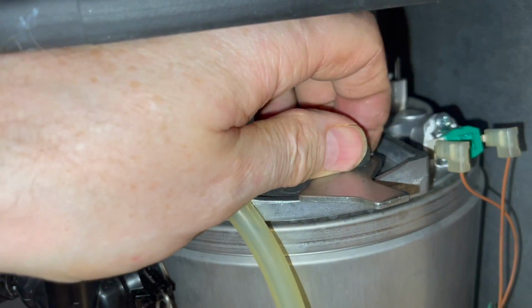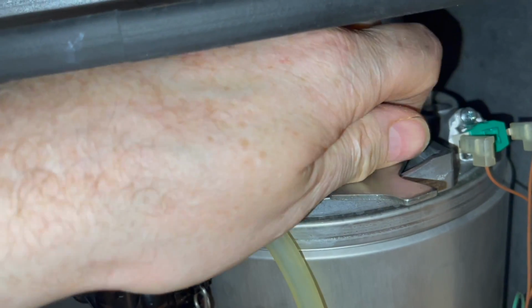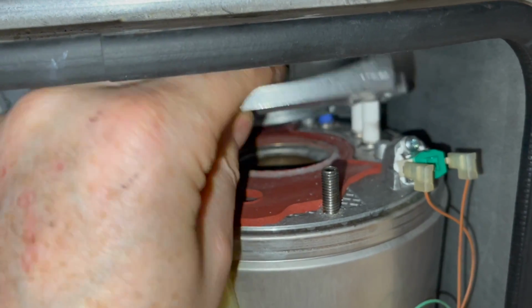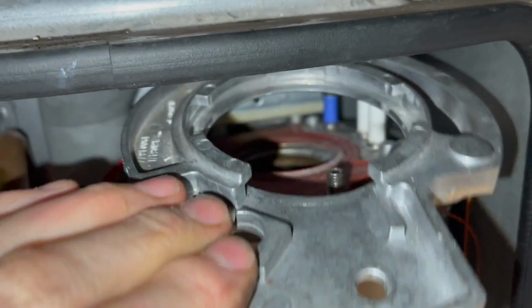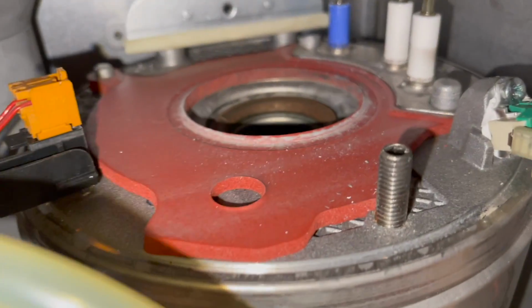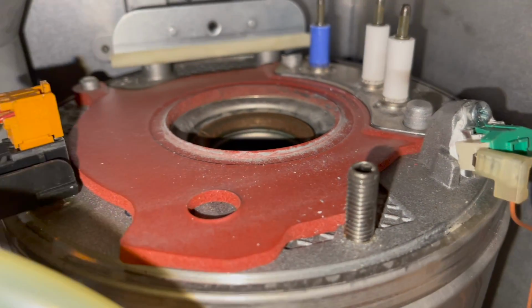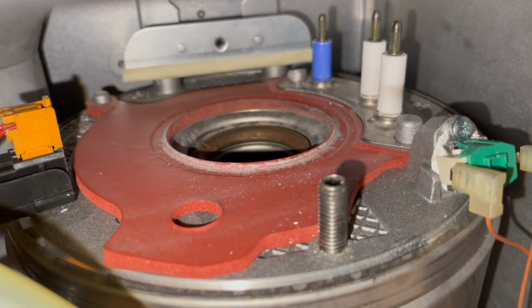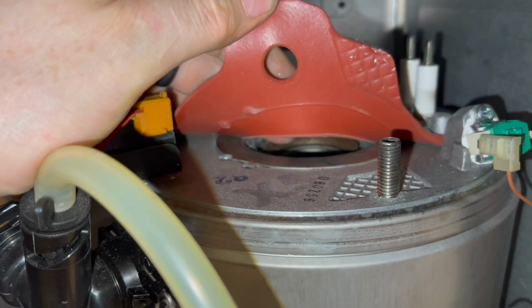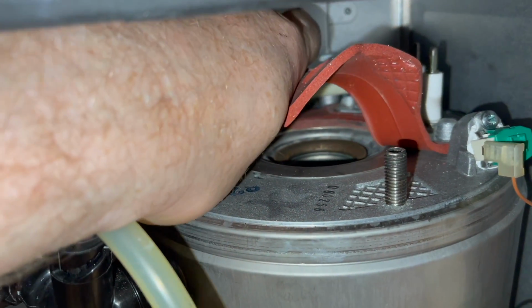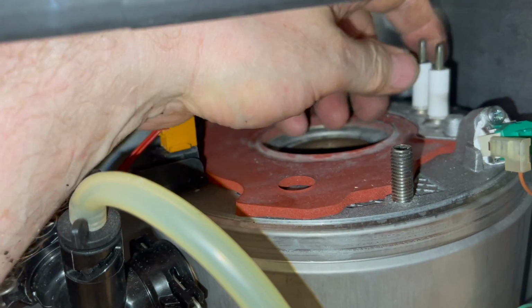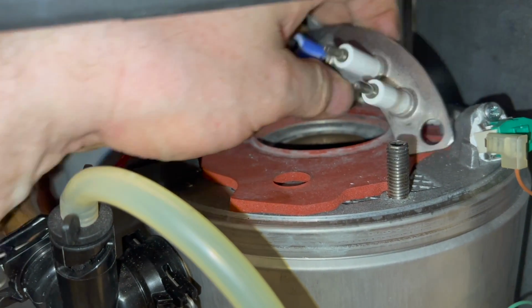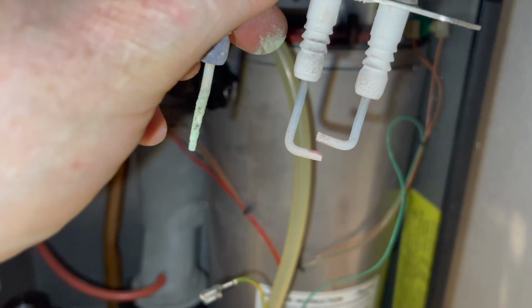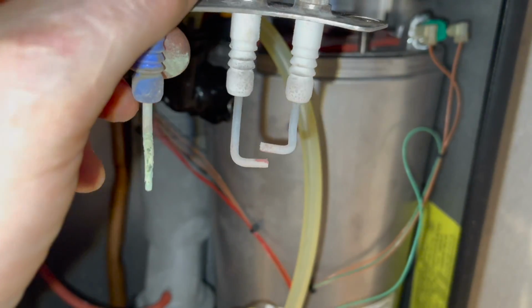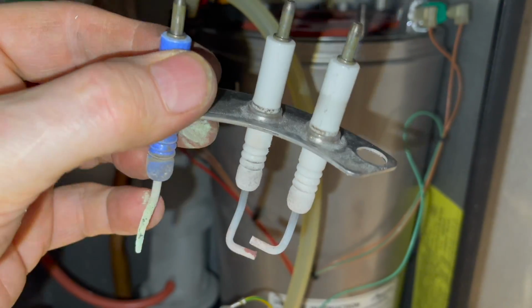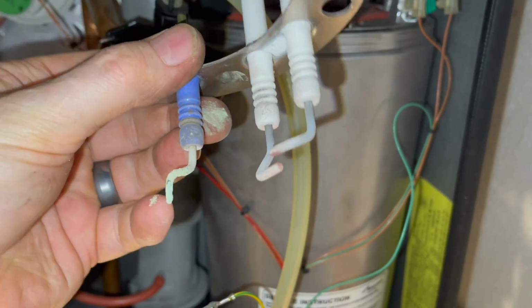Now we can take this nut all the way off, if it comes off. So now the nut's off, we can just lift this out of the way. And you can see that gasket is still in reasonably good condition, but we must change it every time we do this. So now we can remove this gasket. And the electrodes. And again, they're not massively worn, these electrodes. They could actually clean up and go back in, but we get them in the kit, so we might as well replace them.